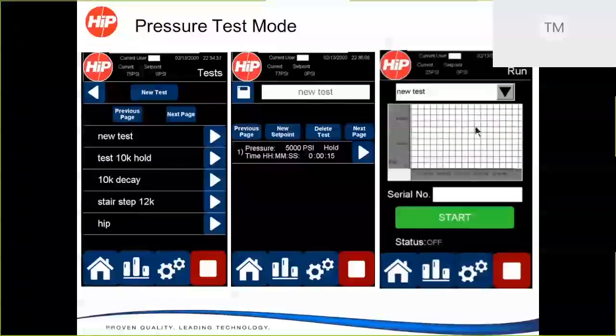To set that up, you push the gear button. There'll be a few icons that'll ask you where to go. You're going to enter pressure test, and it'll take you to a screen where you can enter your test. So if we want to set up a new test, we would hit the new test button. It's going to allow us to enter a name for that test. And then we can do various set points. A set point is a pressure we want to drive to, and we can set numerous ones of those. We can set up to 30 pressures in one given test that we want to drive to.